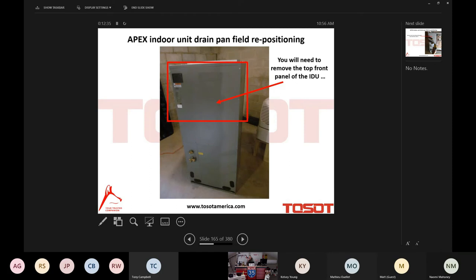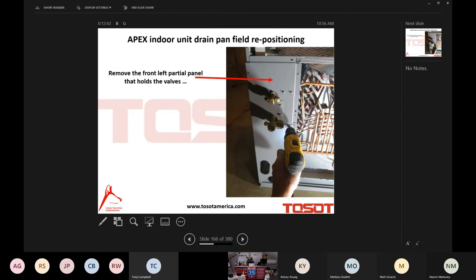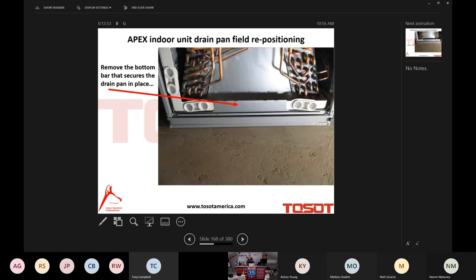We need to remove the entire front panel. Now, the front panel consists of a total of 5 elements. There's the top element, and then the bottom portion, again either 3 or 4 sub-panels, I think, is a good way to describe them. But we need to remove all of the sub-panels. That will expose what I call the brace bar at the bottom of the fan coil. If you notice, it's kind of hard to see, but that brace is actually lipped over the vertical pan for two reasons. So in shipping, the coil doesn't move. And also when you at Emco are manipulating these in your warehouse, and ultimately when your customer's manipulating them at Mrs. Gillicuddy's house, the coil stays in the position that it's intended.